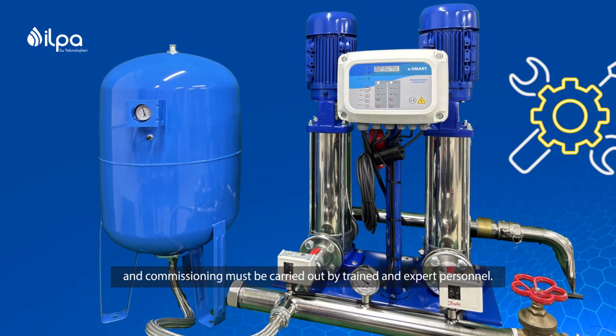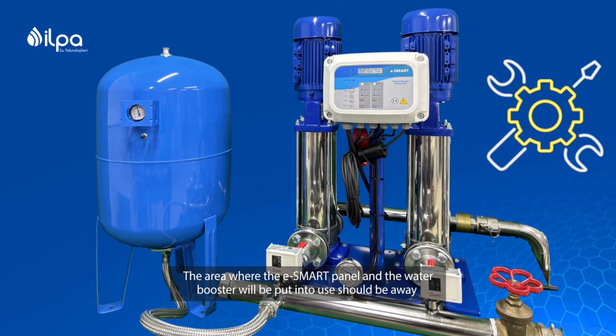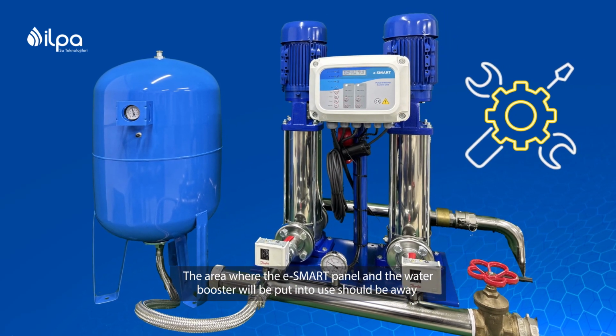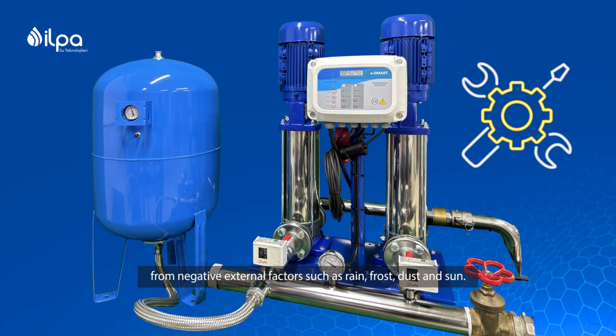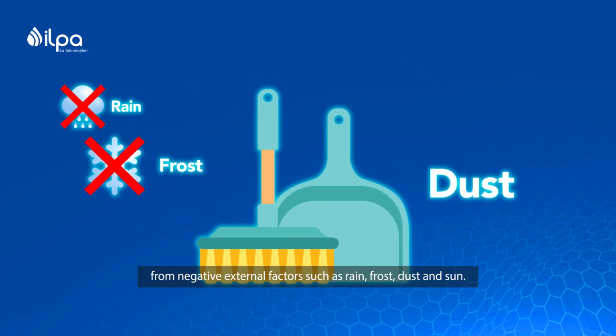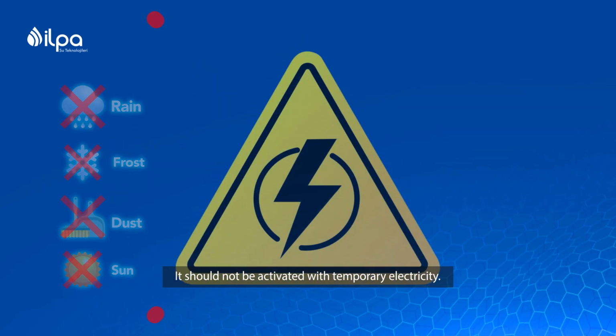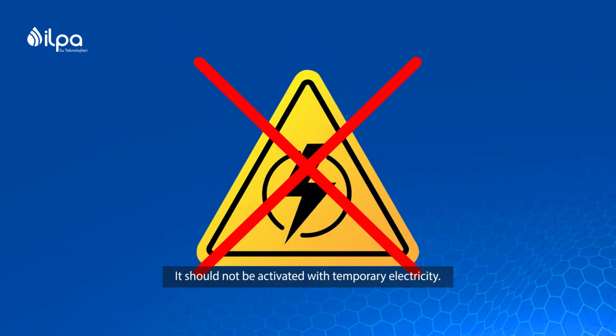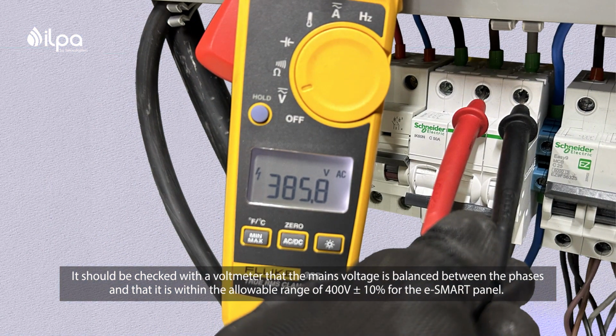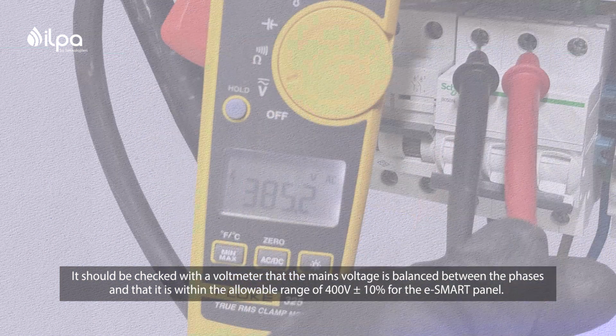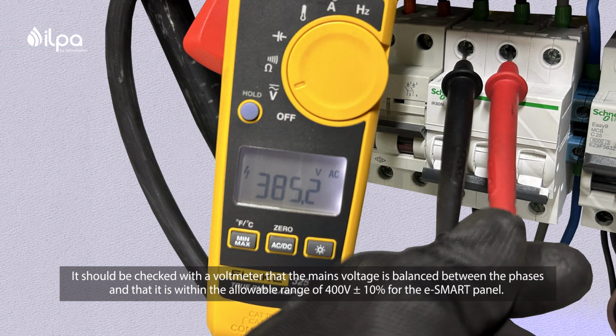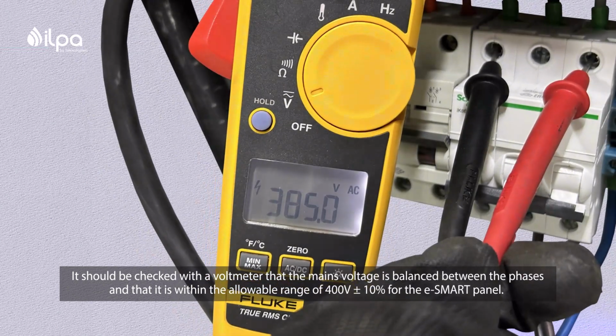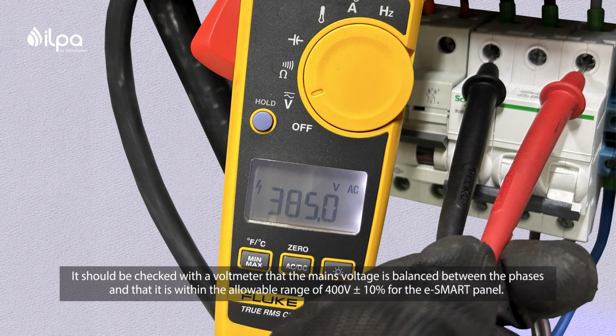trained and expert personnel. The area where the eSmart panel and the water booster will be put into use should be away from negative external factors such as rain, frost, dust and sun. It should not be activated with temporary electricity. It should be checked with a voltmeter that the mains voltage is balanced between the phases and that it is within the allowable range of 400 V plus or minus 10% for the eSmart panel.